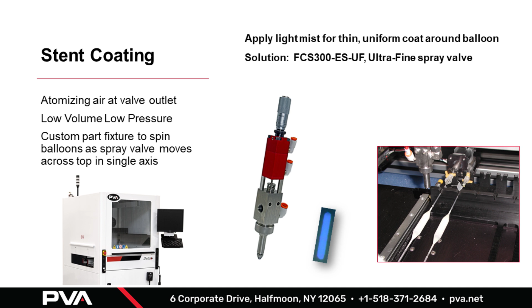the part. In this application, we utilized a custom part fixture inside of a 3-axis PVA machine. This part fixture spun the balloon while the low volume, low pressure atomized spray valve moved across it to apply a very light mist of uniform coating over the top.